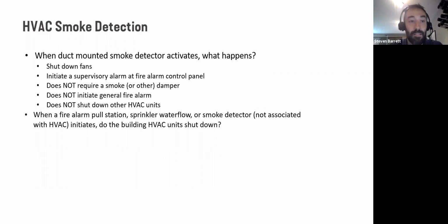It does not require closure of smoke or any other damper. It does not initiate the general alarm. It does not shut down other HVAC units either. The requirement is for that return air smoke detector, or if you're following 90A on the supply side, to shut down the operational capabilities, that's the actual phrasing, of the unit. So typically that means to shut down the fans.